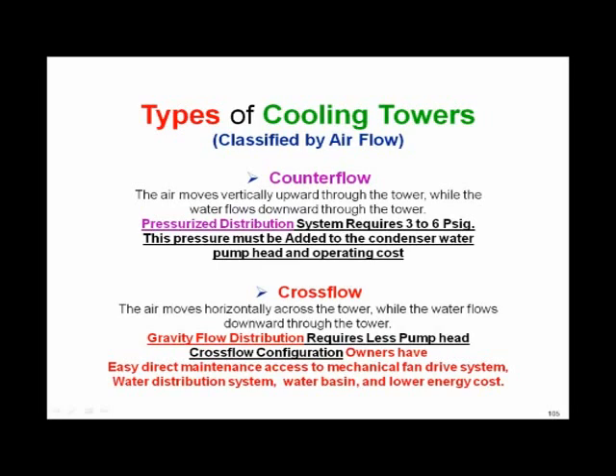Listen to me, please. Take the time to account for the pressure nozzles. You're going to need a safety factor on both, fine, but you can't hide behind the safety factor. You're going to be short if you don't take the time to recognize the difference between the counterflow and the crossflow designs. Both work great, but recognize the pump head requirements on the counterflow will be higher.